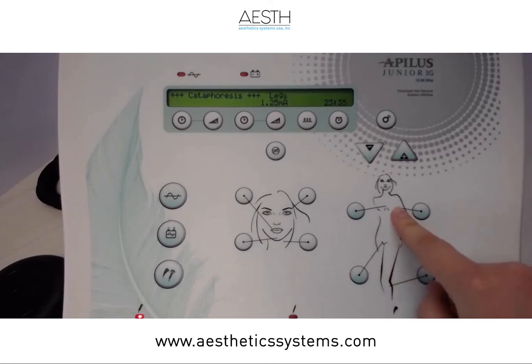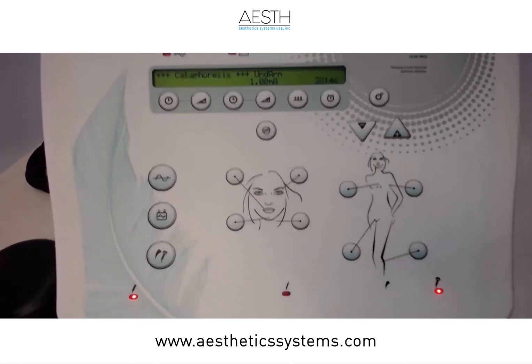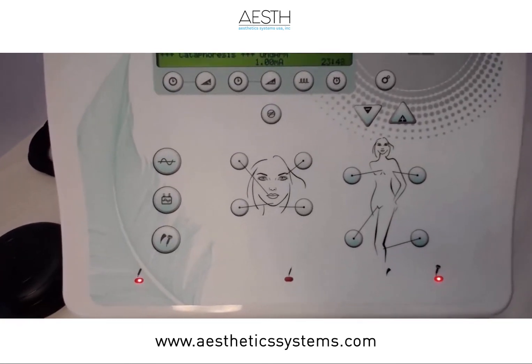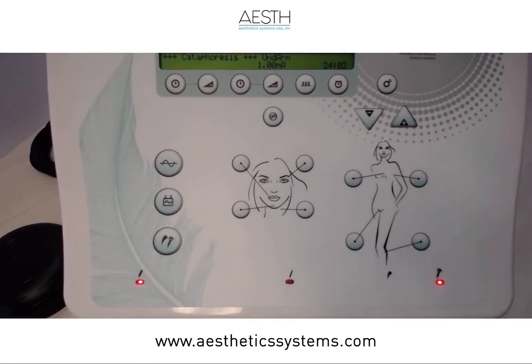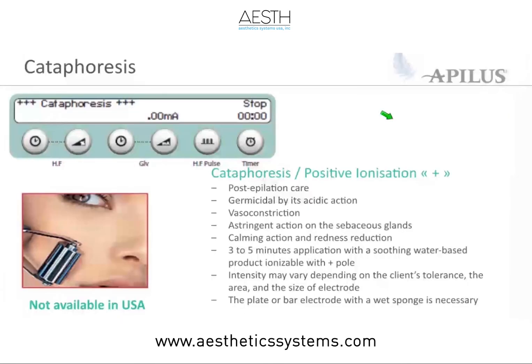So we have a few options here. Depending on where it is, you can see it will change the average amount of mA for cataphoresis. When you do cataphoresis, you'll notice two lights lit up down here: the light for our ground, since cataphoresis is direct current so you need to be grounded, and the light for the wand, because the wand has the handle, and that handle attachment fits the roller. That's what we need in order to do the cataphoresis after treatment.